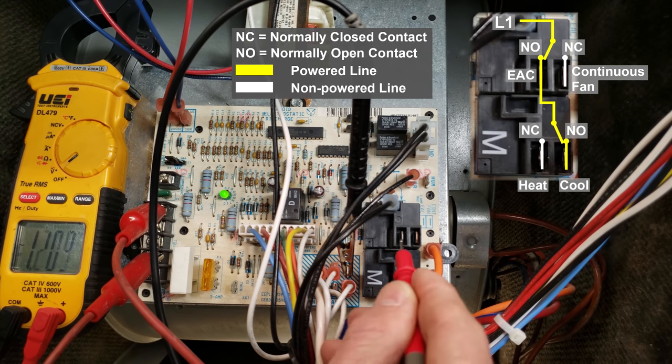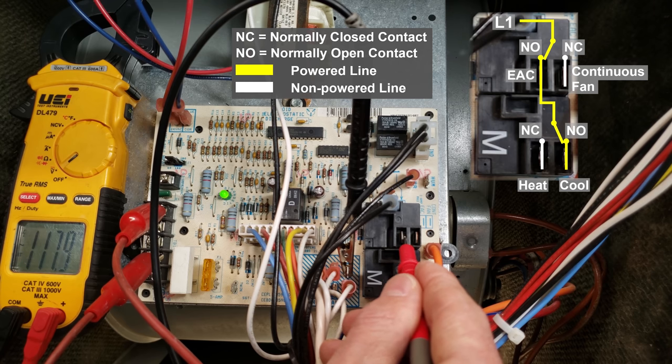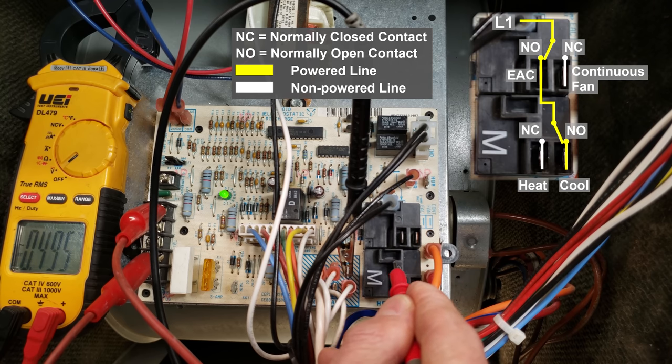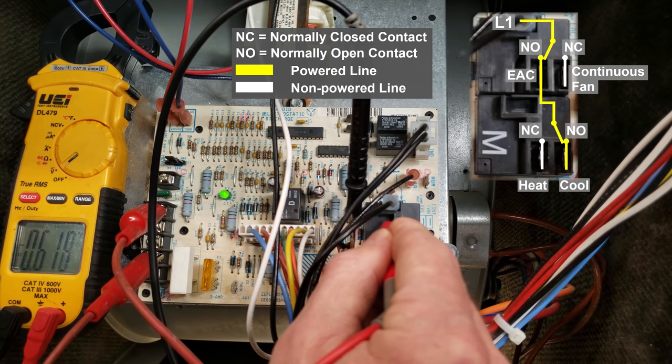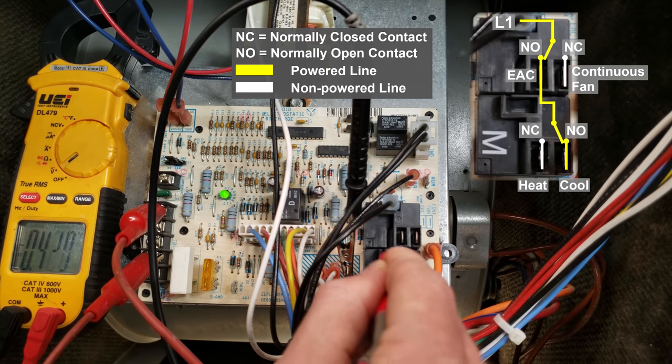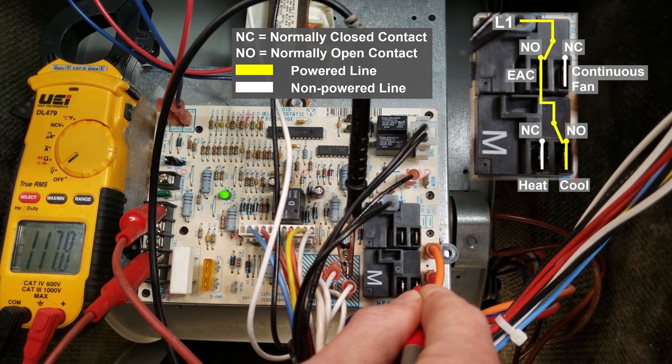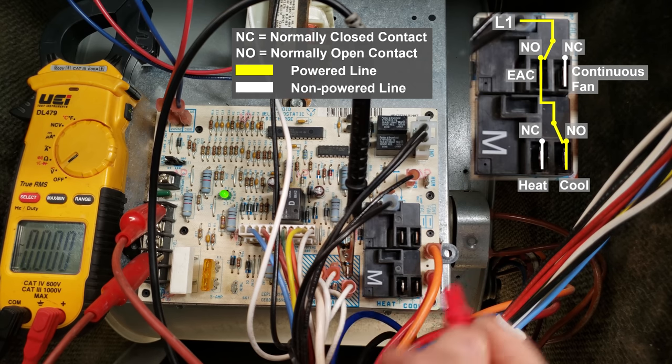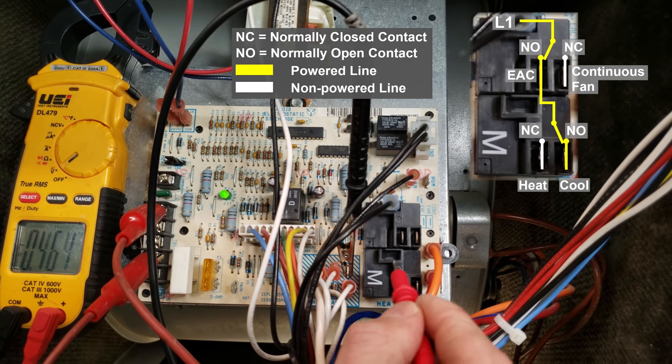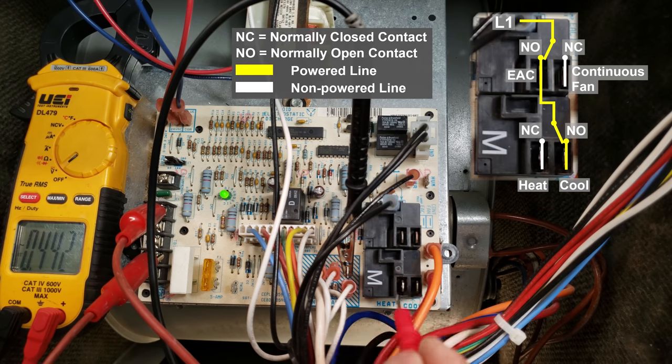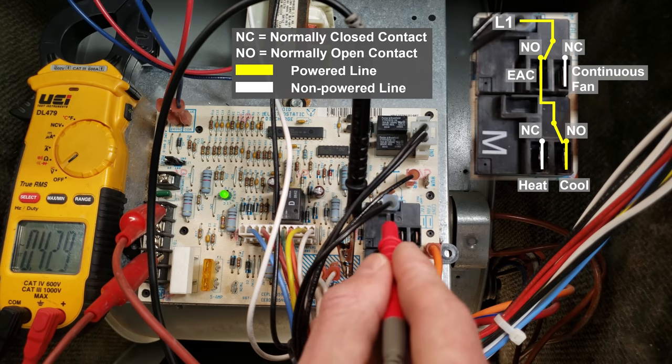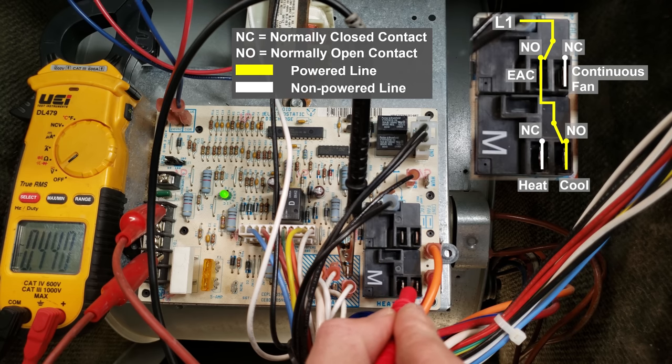Of course we're still going to have this connected to the EAC up here because that's how the power is getting over to here, it's traveling through these contacts over to these contacts. So that's how this works. The main thing that happens with these boards when they fail is the contacts in here, and you can check them by measuring resistance or by looking for a voltage drop across the contacts indicating that you have pitting on the contacts themselves.